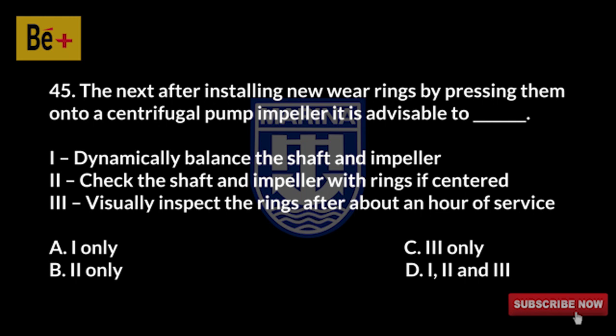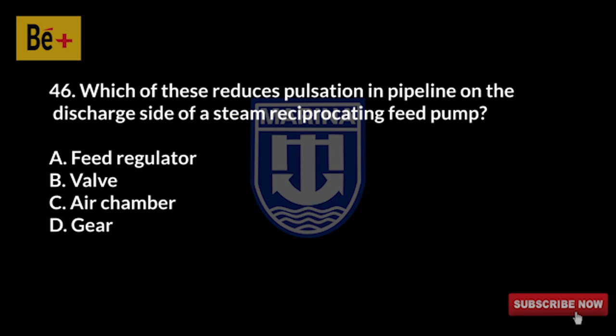After installing new wear rings by pressing them onto a centrifugal pump impeller, it is advisable to: 1) dynamically balance the shaft and impeller, 2) check the shaft and impeller with rings if centered, 3) visually inspect the rings after about an hour of service. The answer is D, 1, 2, and 3.